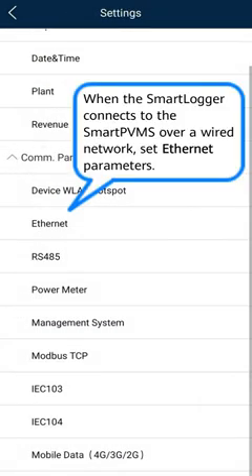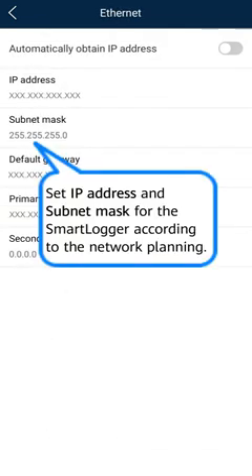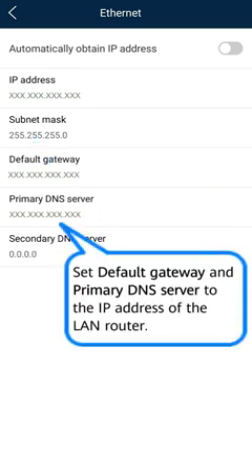When the smart logger connects to the smart PVMS over a wired network, set Ethernet parameters. Set IP address and subnet mask for the smart logger according to the network planning. Set default gateway and primary DNS server to the IP address of the LAN router.